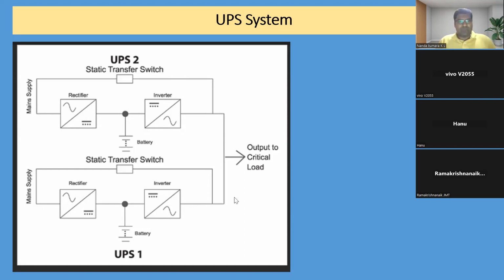Okay, in overall UPS we can think of online and offline UPS, then online UPS comes to parallel configuration. Nowadays, we all know most people talk about modular type UPS. Our conventional type UPS has some technical glitches and lags, so that is why the modular type UPS has come into the picture. With a conventional UPS, the only problem is that if something goes wrong, the entire UPS will be off. It will not degrade the load, but the complete UPS will lose power.